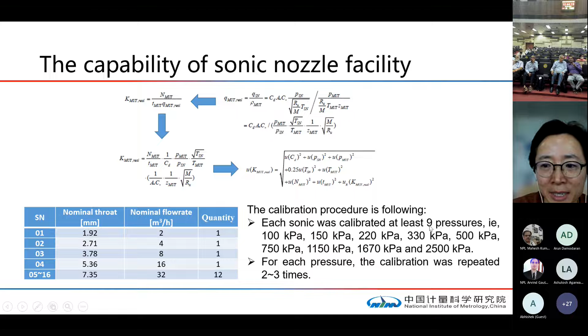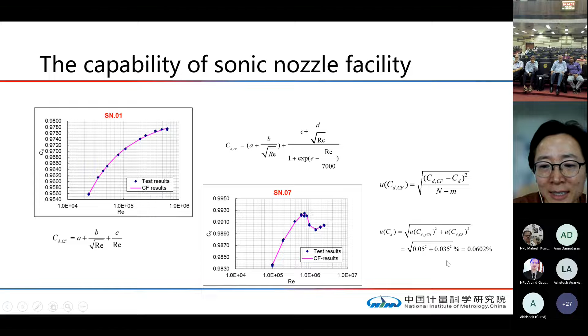So the pressure range is relatively large. And so how to calibrate 16 sonic nozzles, how to achieve the best uncertainty for the nozzle is the biggest challenge for the sonic nozzle facility. Finally, for each nozzle, we calibrate at least 9 pressure points. And to achieve the best uncertainty for each nozzle, we make the curve fit on the base of the calibration result. And the curve fit formula is chosen according to the principle of the sonic nozzle. Finally, you can see here the residue for the curve fit is relatively small.